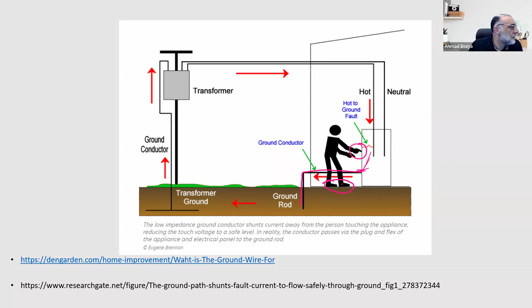This leads us to the subject of grounding. We need to ground electrical components, devices, and machines, so that in case of any failure or fault, the current never flows through your body. It goes instead through this direct line of low resistance, made of very conductive material, which the current will always prefer over your body.